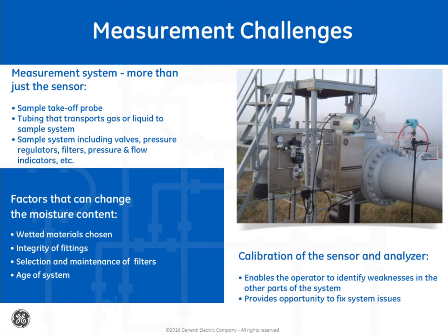Consider that all these system attributes may impact the accuracy and overall health of the measurement. All analyzers and their sensors are subject to process contamination that may impact speed of response and accuracy. Even the best sample systems are subject to process upsets, such as plugged filters, saturation with water, unexpected contamination, and leaks caused by vibration and or corrosion. All of these factors that may impact the measurement system can lead to the operator questioning the veracity of the sensor's readings. Calibration of the sensor and analyzer enables the operator to clearly identify the weaknesses in the other parts of the system. It offers the opportunity to investigate and clear any of these potential issues.